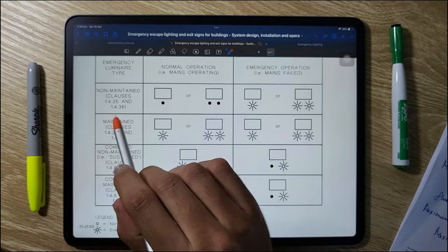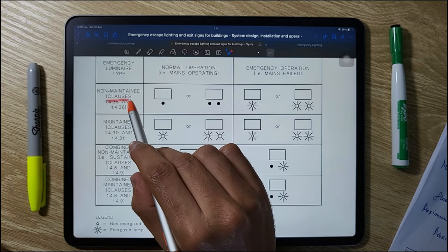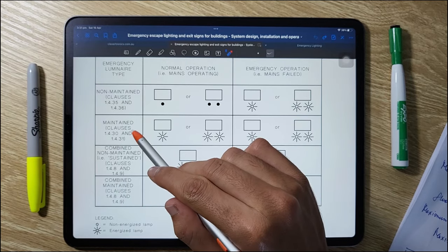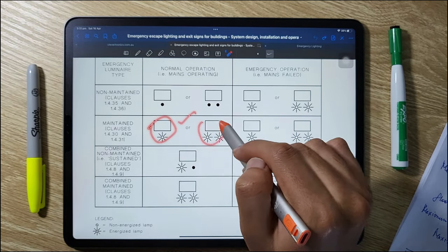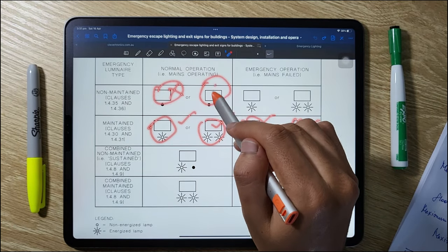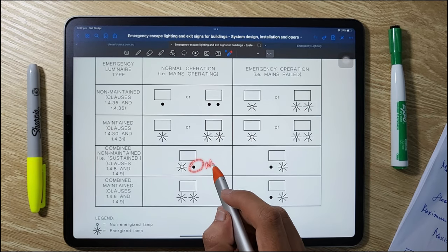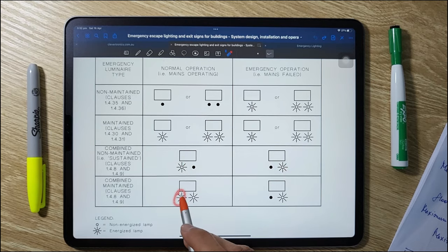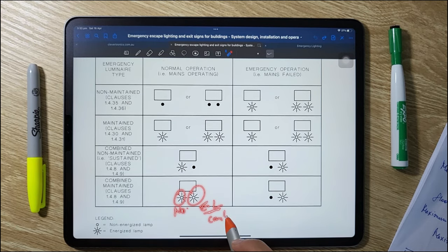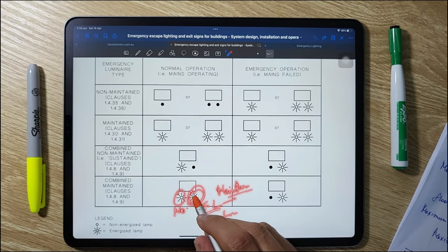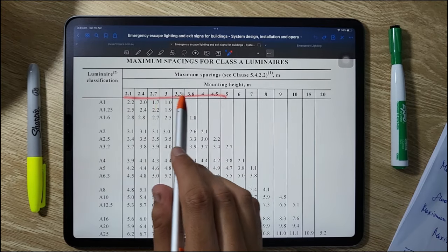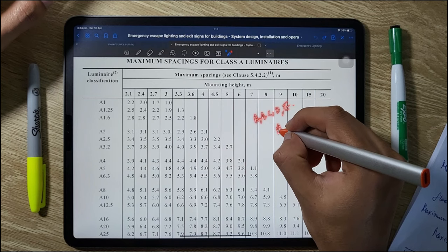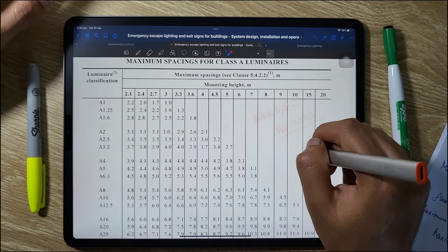Under non-maintained operation, the LED luminaire does not work during normal operation but is powered by battery upon mains failure. Maintained luminaires work at all times — during normal operation and during mains failure. The third option is non-maintained combined luminaires, with one non-maintained and one normal luminaire; upon mains failure the normal luminaire stops and the non-maintained luminaire operates from battery. The fourth setup has one normal and one maintained emergency luminaire — both work under normal operation, but only the emergency luminaire works on mains failure. Classification A, B, C, D, and E is also specified in AS 2293 standards, along with the distance between luminaires.